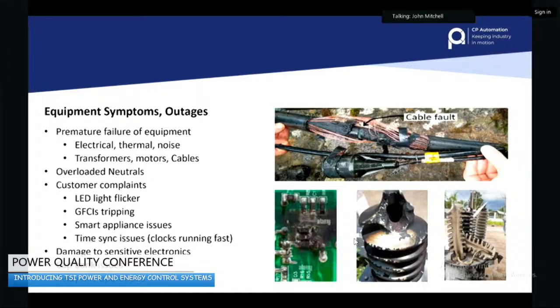But basically, capacitor banks will fail, especially if they're not detuned, due to harmonics and other things, transient spikes in the cable. Anywhere you hear that your customer has a fire is a great opportunity to get involved with your client and help them, because a fire is typically a prime example of harmonics and transient problems related to the site.